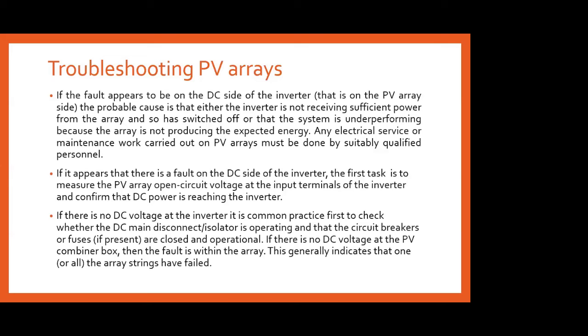If the fault appears to be on the DC side of the inverter, what we have to do? The probable cause is that either the inverter is not receiving sufficient power from the array. If the inverter is not receiving sufficient power from the array, then of course your inverter will go to the off condition, or it may be in an under performance condition. If it is under performance, then I have to check my PV arrays itself. In that particular case, any electrical service or maintenance work carried out at a PV array must be done by suitably qualified personnel. So if we are not getting a sufficient amount of power from the PV arrays on the DC side, we have to make sure that the troubleshooting is done from the PV arrays itself.